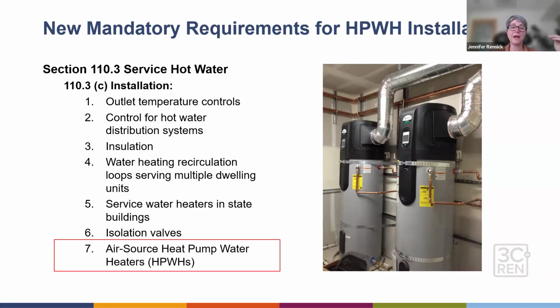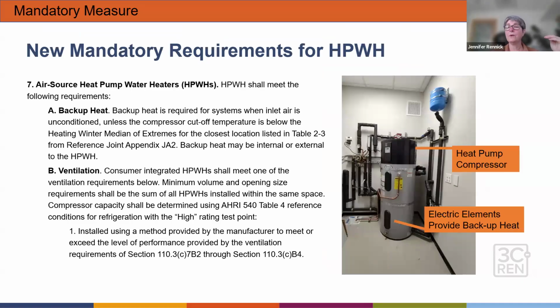And when we take a look at that section, now we are delving into some of the requirements, and I put the text here for you because, you can go back, you're going to get a copy of the slides, you can review it, and it was just here to be convenient when you get a copy of the slides. But one of the main things, first off, is they say, well, you have to make sure your system does have some backup heat because there are operating parameters for heat pumps in terms of temperature control.